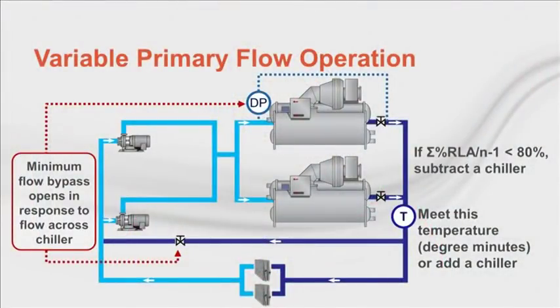Now, if we manifolded our pumps together, not only are the pumps redundant, we may be able to run more pumps than chillers. The number of pumps to run is more or less independent of the number of chillers to run. In this system, we delay adding a chiller automatically, as the pumps are driven by the load and ramp up well past what would perhaps have been the design flow rate of the chiller. The minimum flow bypass opens whenever the flow across the chillers is below minimum. We can use a flow meter or a chiller differential water pressure to determine when this happens.